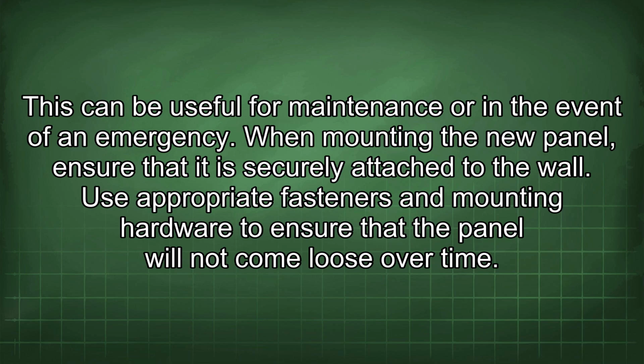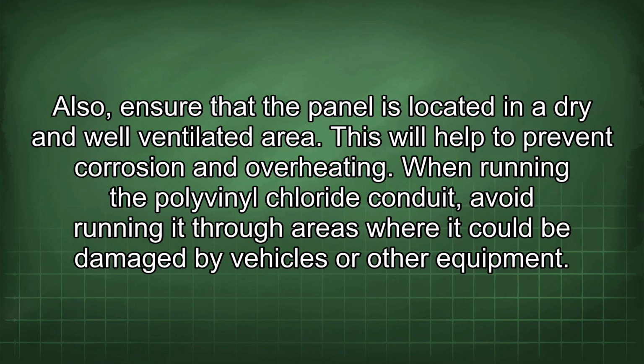When mounting the new panel, ensure that it is securely attached to the wall. Use appropriate fasteners and mounting hardware to ensure that the panel will not come loose over time. Also, ensure that the panel is located in a dry and well-ventilated area. This will help to prevent corrosion and overheating.